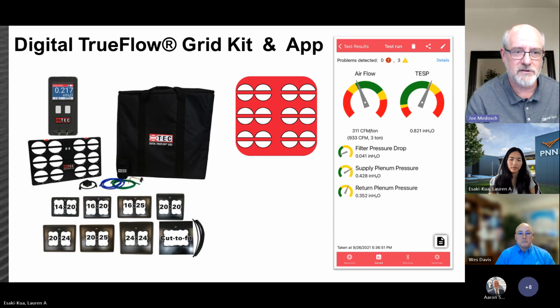If we're not going to do a great job measuring airflow, we're going to fail at making heat pumps work because of the ducts already installed in existing homes. I know the TrueFlow Grid is working on an update for their app to help people figure out if a system will be adequate for the new heat pump they want to install - is this duct system adequate?